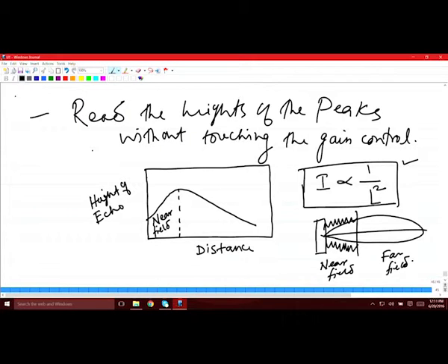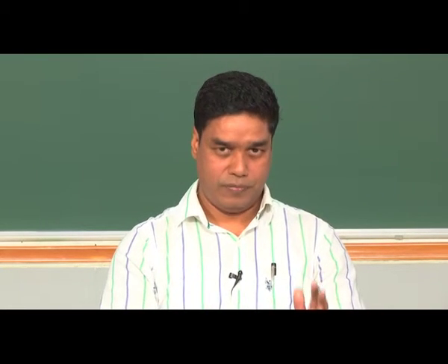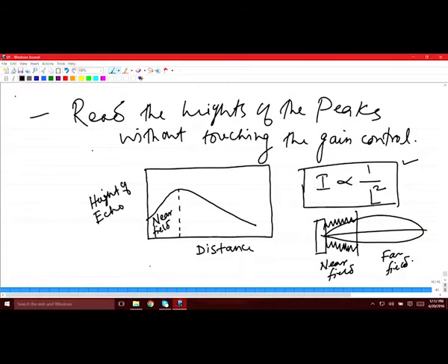with increasing distance is the near field, because as I told, in the near field if you increase the distance the receiving is better, because the probe will have longer time for all these fluctuations to come down and then it will be ready to receive. Okay. So, as you increase the distance in the near field, the receiving would be better and the signal intensity would be higher. Okay. So, that is exactly what you see in this distance amplitude curve. Okay.